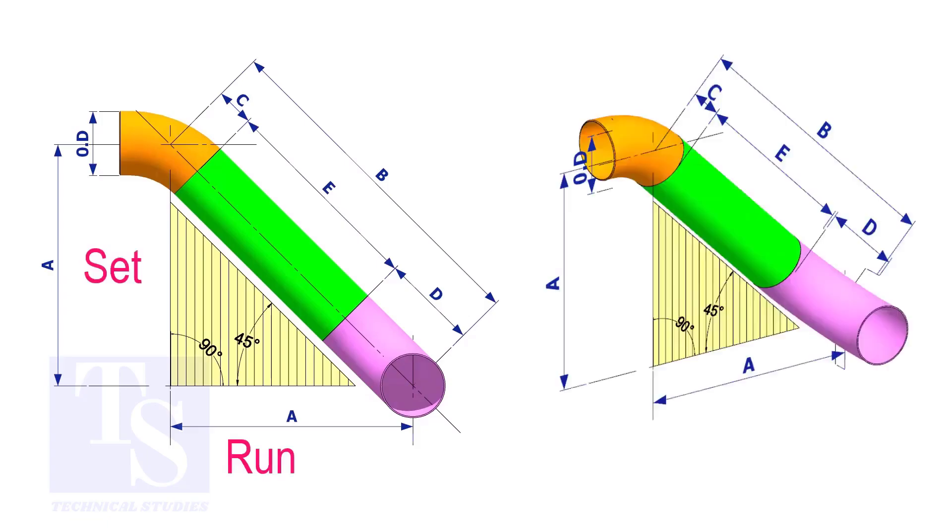In an offset, if the included angle is 45 degrees, the set and the run shall be the same. If the value of the set and the run are equal, the value of the travel is set or run multiplied by 1.414.